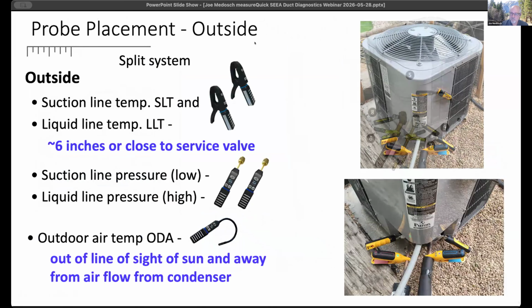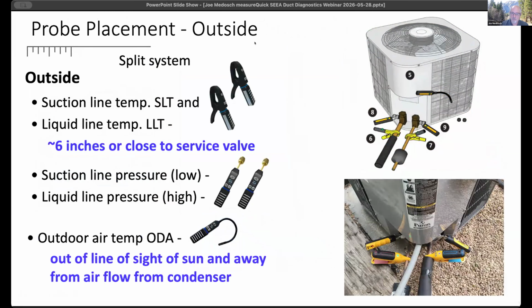These are what's outside. So I had 4 inside, and these are my outside probes. I'm basically just measuring the refrigerant pressures and temperatures, and I have an outdoor air temperature, which gives me guidance as to how well everything is performing. Those are all of the 9 probes that you need. Once all those 9 probes are on and the system is at its full capacity, then I can give you great diagnostics as to what's going on or what the problems are.